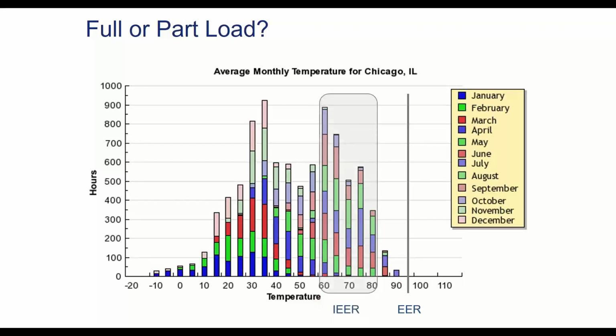Whereas these hours where it's 65, 70, 75, 80, 85 degrees outside, those are where I spend all my time running. Each one of these lines is 100 hours of runtime per year. So just on the 60 to 65 line, we have almost 900 run hours at just that 5-degree band, right? So you start adding all this up, and all the time is spent at part load and almost nothing at full load. So essentially, we've all concluded full load is almost irrelevant. So part load efficiency is where the action's at.